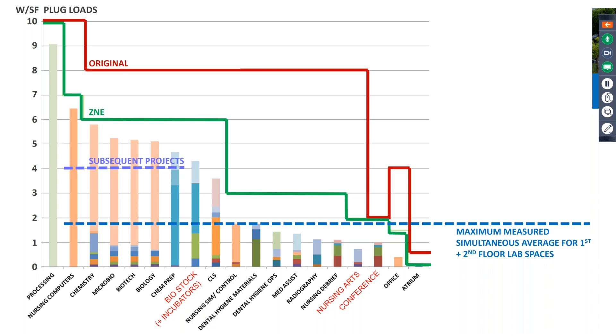But by doing this detailed study, we were able to more accurately define those loads and reduce the wet labs down to 6 watts per square foot and the dry spaces down to 3 watts per square foot. We've since been monitoring the actual operating data, and if you take the entire second floor looking at the wet labs and the support spaces, it's actually on average never exceeded 1.75 watts per square foot. So subsequent buildings we're now designing at 4 watts per square foot instead of the 6.